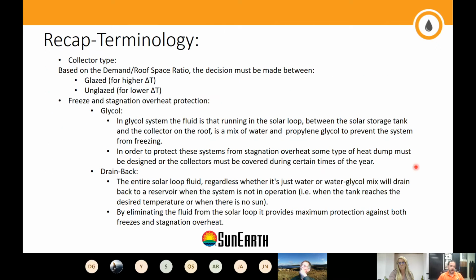Once that's decided, we talk about what type of freeze protection and stagnation overheat protection we're looking at. For direct systems, freeze recirculation is a good option, but isn't covered here. Otherwise, there are two main categories for freeze protection and stagnation overheat protection: indirect glycol systems or drain-back systems.